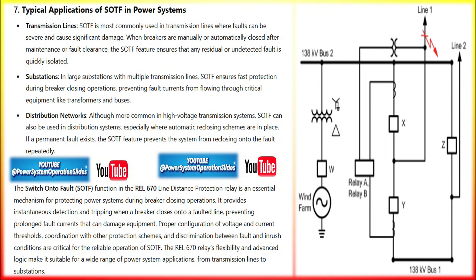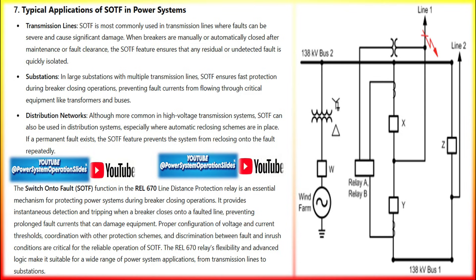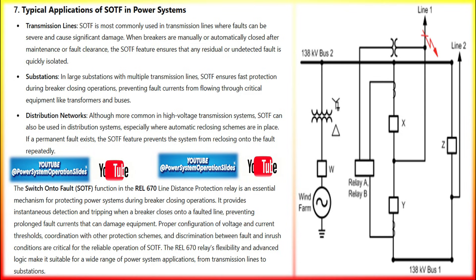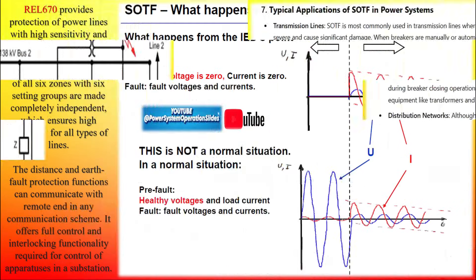Post-fault detection: once the breaker closes and the circuit becomes energized, fault current flows immediately. The SOTF logic uses a high-speed current detection element that measures the fault current magnitude instantly upon breaker closure. The relay does not wait for zone-based protection calculations, which may take a few cycles; instead, it sends an immediate trip signal to the breaker if fault conditions are detected.